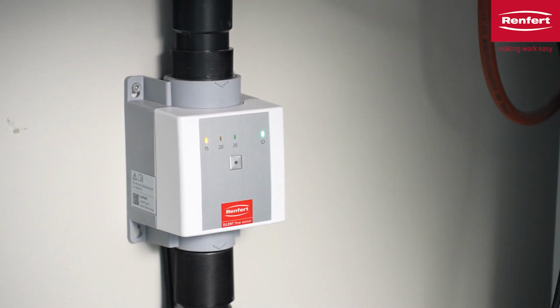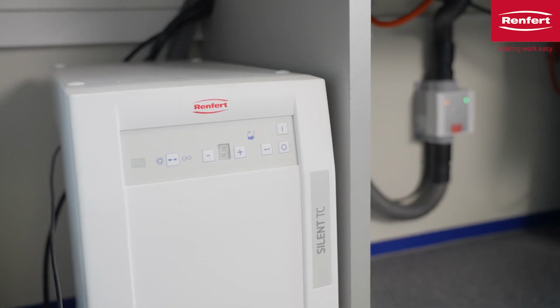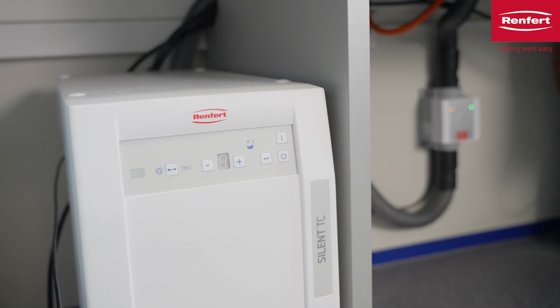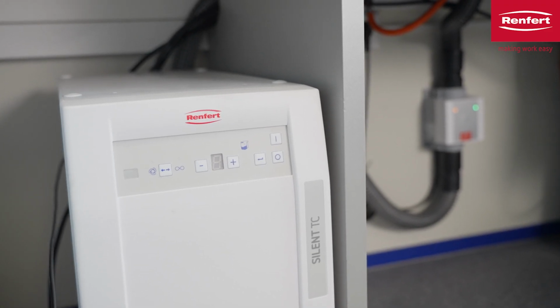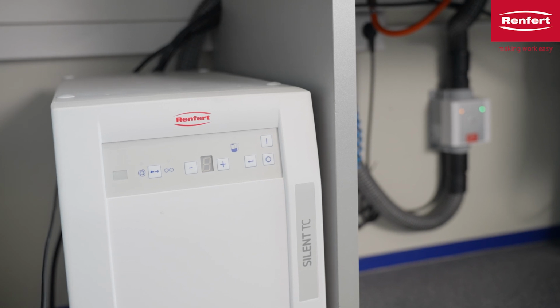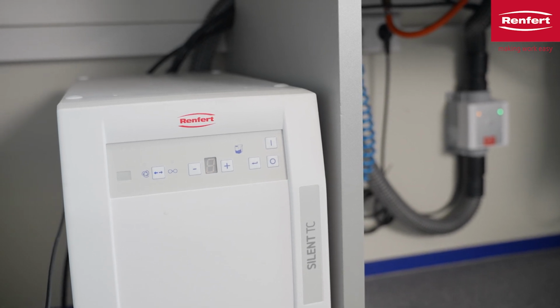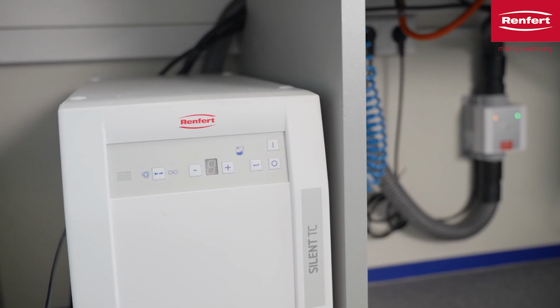Release the button. The displays flash alternately. The zero adjustment is performed. After approximately 5 seconds, the silent flow sensor returns automatically into operating mode. The zero adjustment is completed.